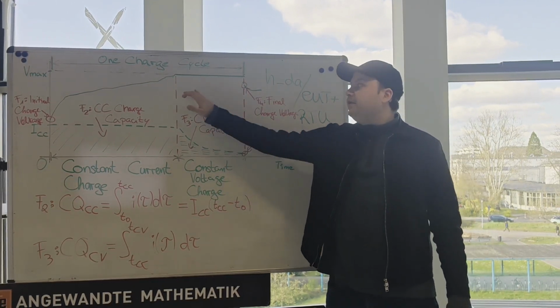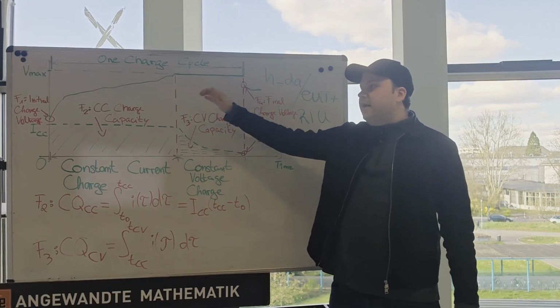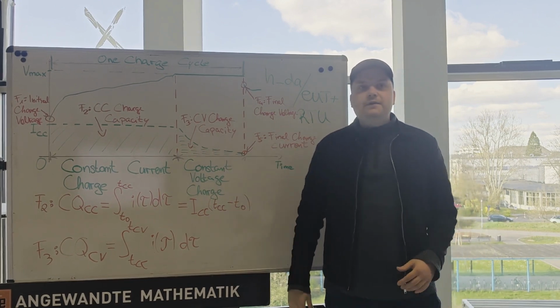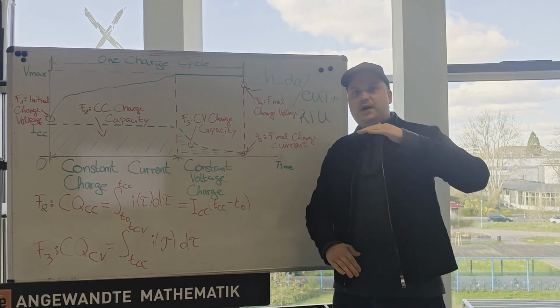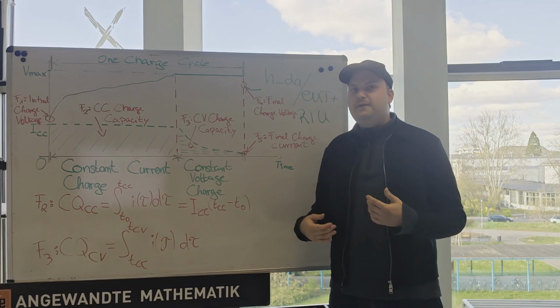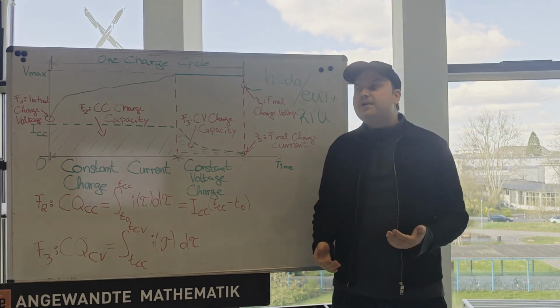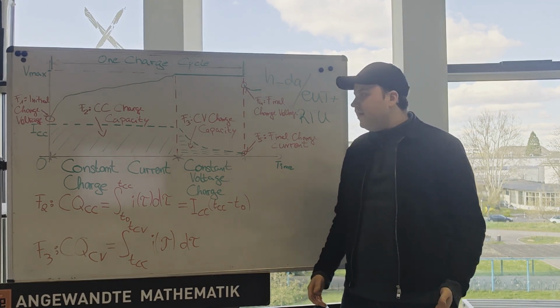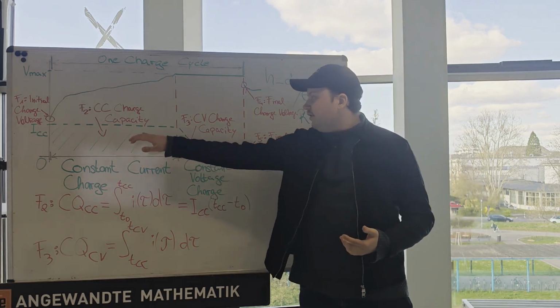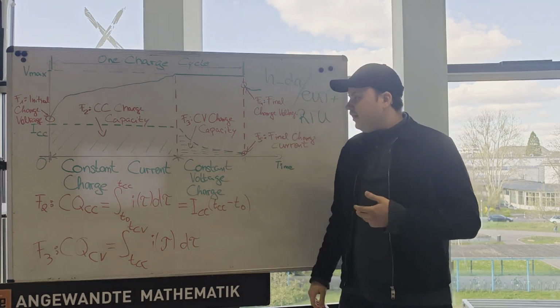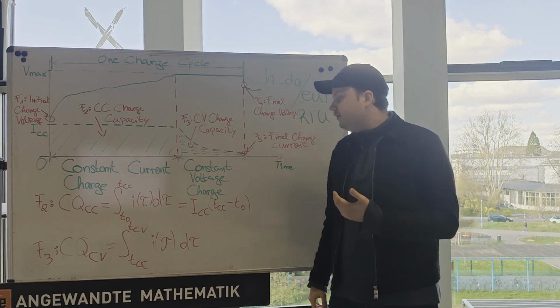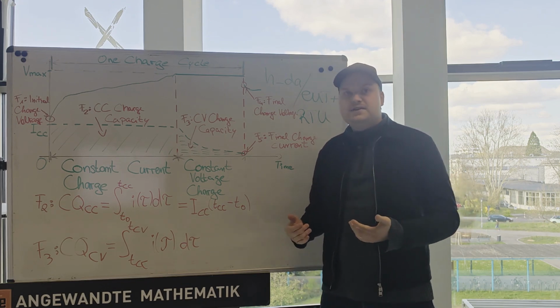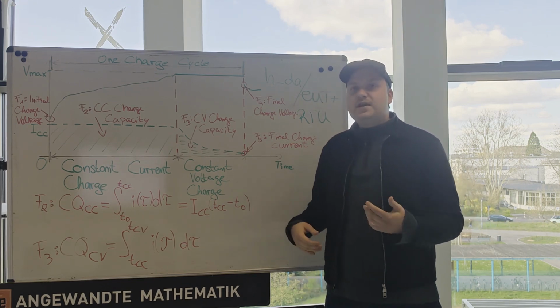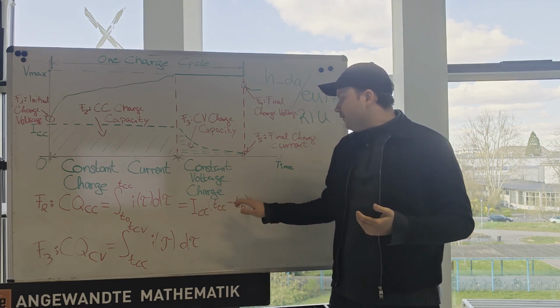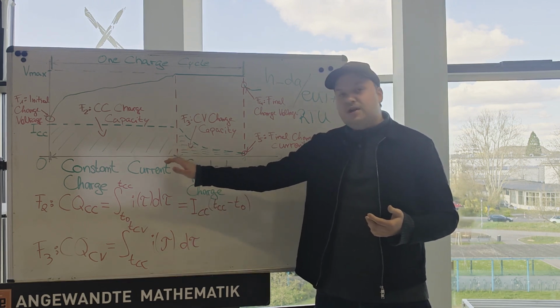In the second phase, the voltage stays constant at its maximum value and the current is falling. If we were to always charge from 0% to 100%, this would already be enough information. We just calculate the constant current and constant voltage charge capacities. This can be done by taking the integrals over the respective time frames. Especially for the constant current charge, this is relatively simple because the current is, as the name implies, constant. We just multiply the current with the time interval from when we stopped charging with constant current to when we started charging it.